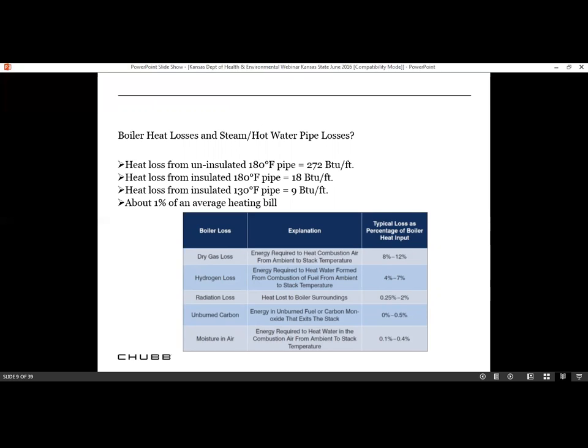non-insulated piping. And one of the other things, and Keith had mentioned this too, if you look at the graph or the bullet point there, it says unburned carbon. Energy in unburned fuel or carbon monoxide that exits the stack. That is a real key, and that's why we recommend doing combustion analysis several times a year, just to make sure that we have optimum combustion and that the fuel to air ratio is perfect, because it could cause sooting, and that will increase your cost.